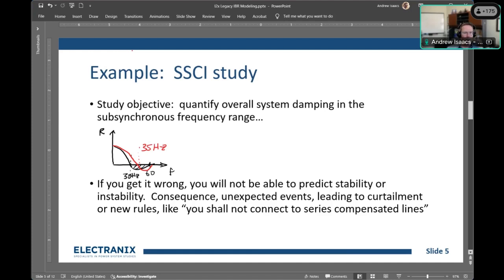That difference in the frequency scan can come down to a control parameter in a highly accurate model. If you take one of Miguel's beautiful models, parameterized straight from the source code, a small change in the parameters—same turbine, same hardware, but tuned slightly differently—can shift this damping characteristic enough to pass or fail the plant.